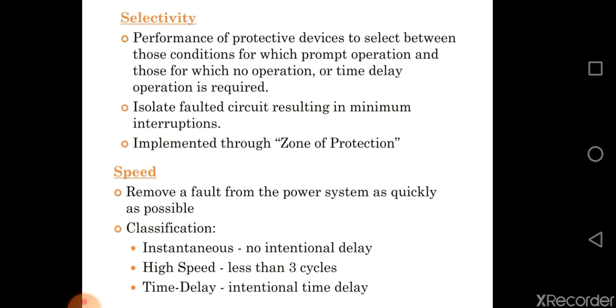Selectivity. Performance of protective devices to select between those conditions for which prompt operation and those for which no operation or time delay operation is required. Isolate faulted circuit resulting in minimum interruptions. Implemented through zone of protection. Speed. Remove a fault from the power system as quickly as possible. Classification. Instantaneous, no intentional delay. High speed, less than 3 cycles. Time delay, intentional time delay.